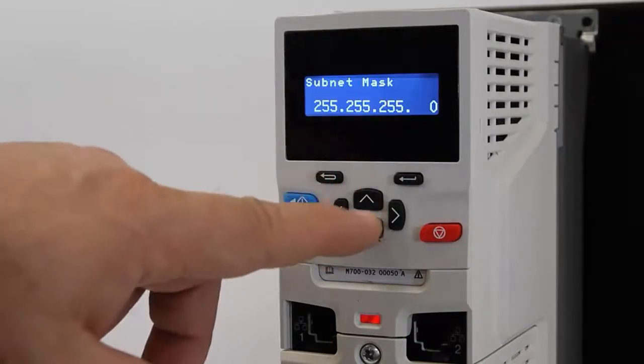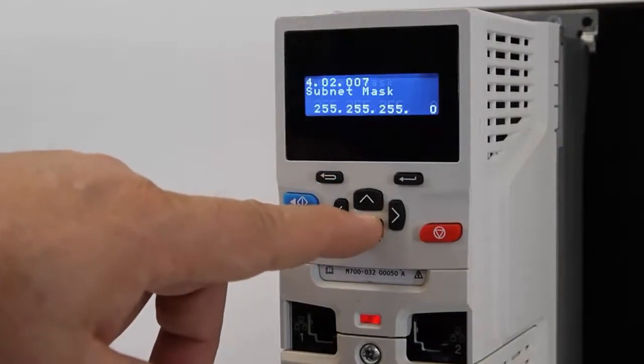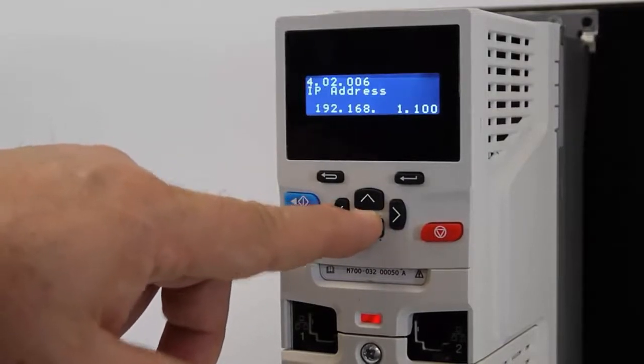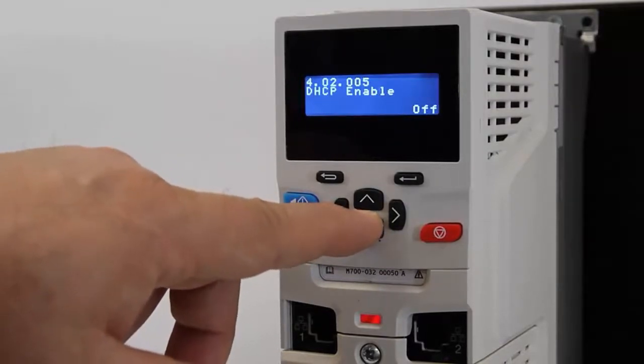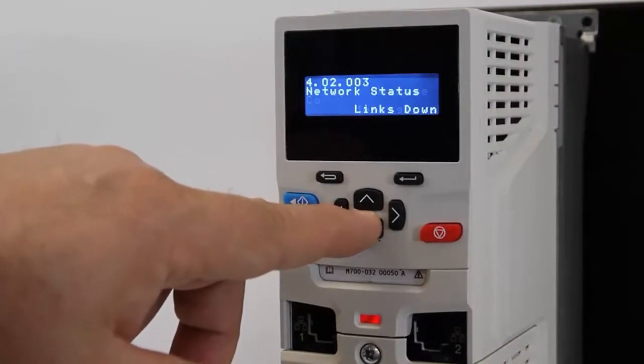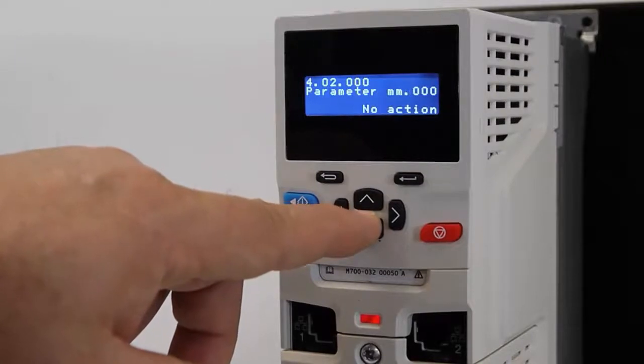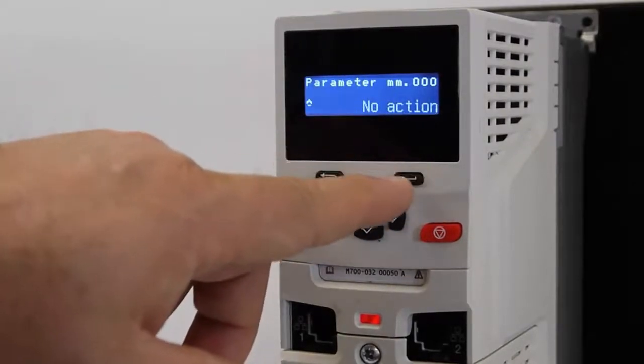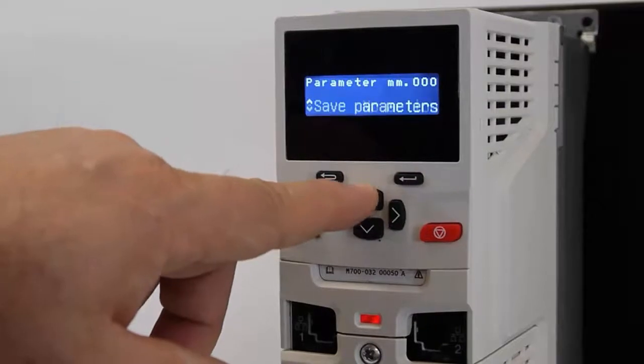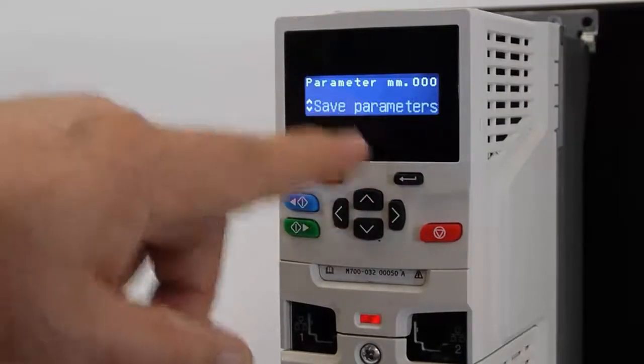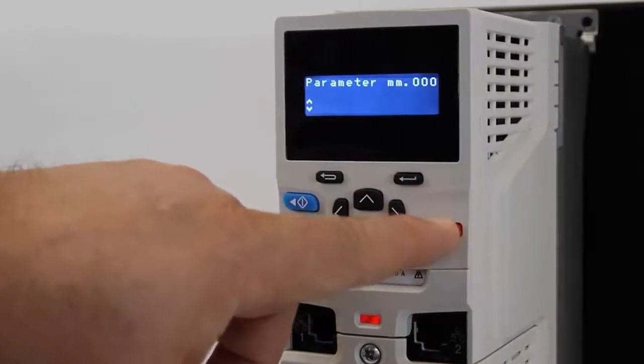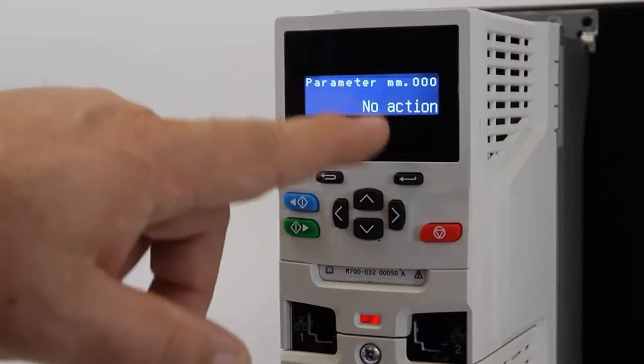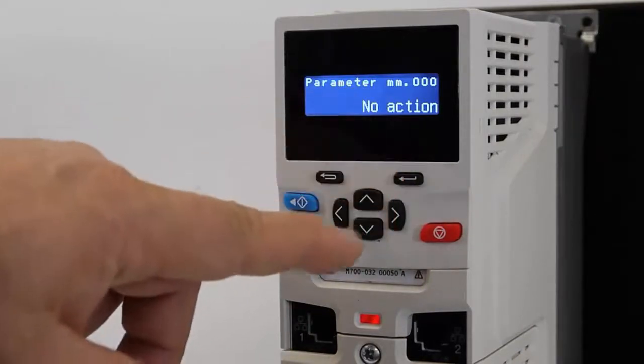Next, I'm going to save the parameters by going to any parameter 0. Since we're already in menu 2, I'll use the down button until I get to parameter 0. I'll press enter, then the up arrow one time for 'save parameters,' and then the reset button. When it says 'no actions,' the parameters have now been saved.